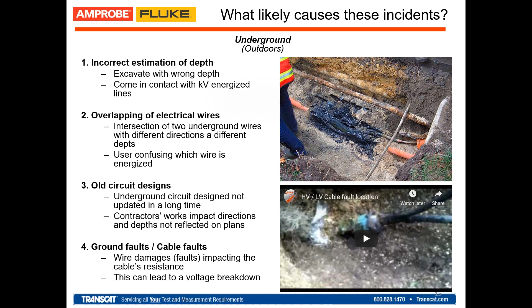I also want to spend some time on ground faults, for the sake of economic analysis of how bad they are—less of a safety issue, though safety issues are definitely catastrophic. But ground faults definitely become an operational issue, because when you have a ground fault or cable fault, you have a non-operational circuit.